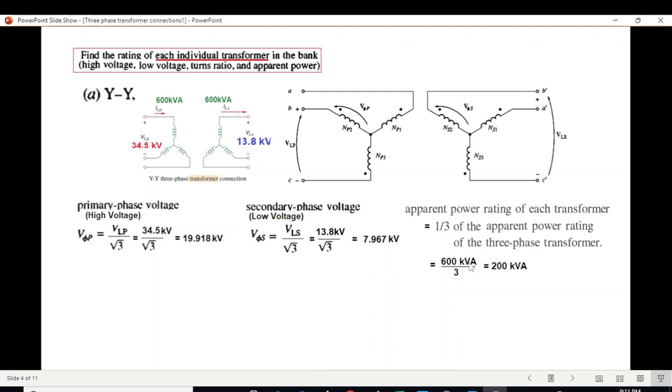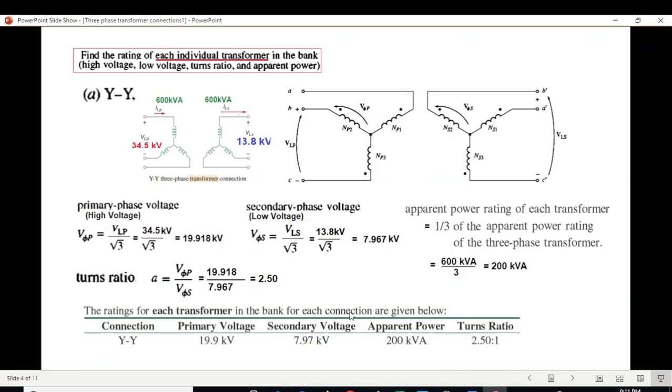The apparent power rating of each transformer will be one-third of the apparent power rating of the three-phase system. Total power rating given is 600 kVA divided by 3 equals 200 kVA apparent power of each transformer. Finally we calculate turn ratio as V_primary divided by V_secondary, which equals 2.5. In table form: Y-Y connection primary voltage 19.9, secondary voltage 7.97, turn ratio 2.5, apparent power 200 kVA.